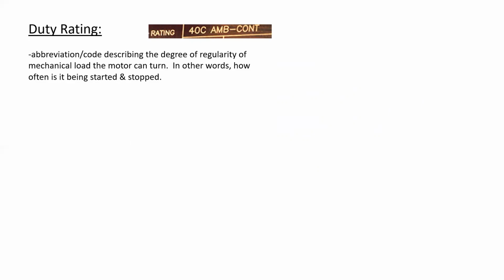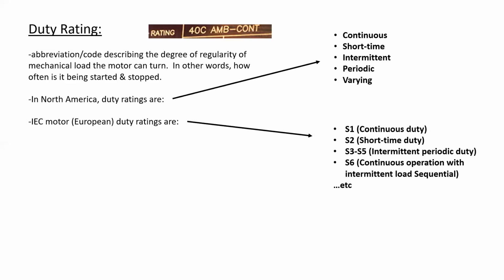A motor that's started and stopped continually will actually be exposed to significantly higher degrees of heat than a motor that simply runs. Now, in North America, duty ratings are in a word form: continuous, short time, intermittent, periodic, varying, and they will sometimes have a time also associated with them, but that wording will be on the nameplate. In European spec motors, the duty ratings are an alphanumeric code that we would then look up through the manufacturer. You do not have to memorize the European or the standard North American duty ratings, but you do need to have an appreciation for what it represents. The duty rating is also used when determining the minimum conductor size for the motor, as per Section 28 of the Canadian Electrical Code.